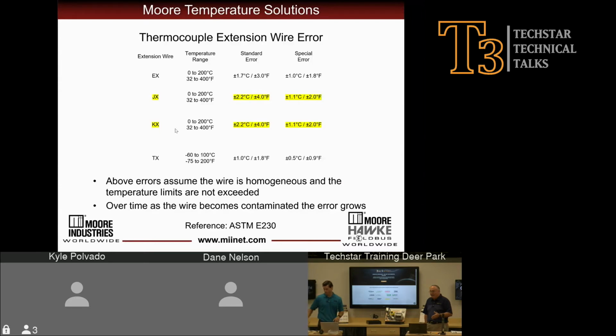There's an adder, and typically the way that Moore would do a certification is they would put it in a temperature bath and give you the actual readings out. And you could also go ahead and order matched so that your 4 to 20 milliamps would equal that and you get a cert. Yes, yes. Other than that, if you don't, then you just get the standard thermocouple table. Yeah. So plus minus 4 degrees. Upon request, we will deliver a certification of the calibration of any sensor and transmitter as well. So we can provide that.